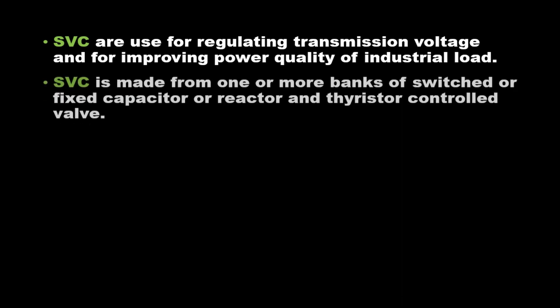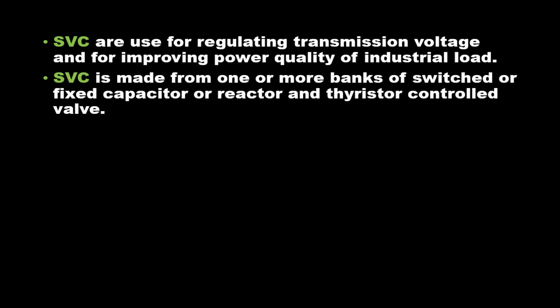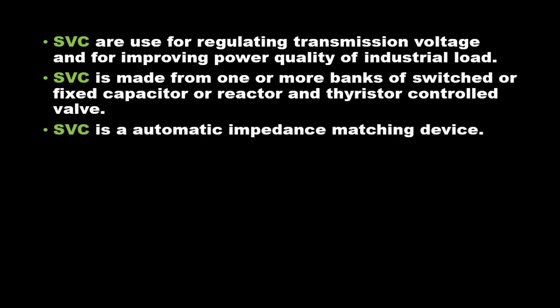Static var compensator, SVC. SVC are used for regulating transmission voltage and for improving power quality of industrial load. SVC is made from one or more banks of switched or fixed capacitor or reactor and thyristor controlled valve.